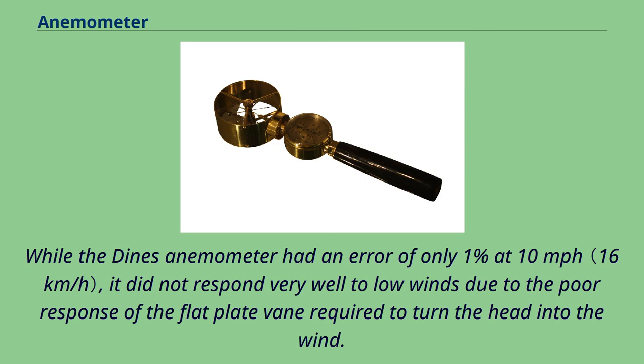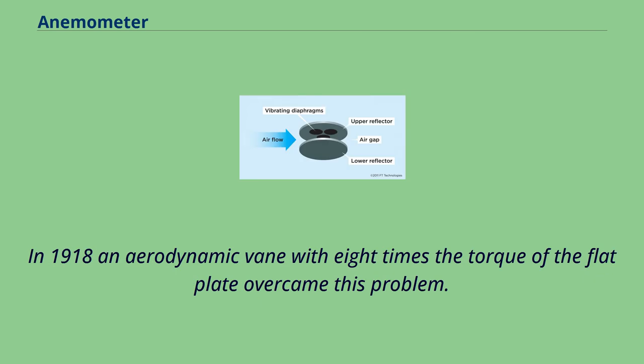While the Dines anemometer had an error of only 1% at 10 miles per hour, it did not respond very well to low winds due to the poor response of the flat plate vane required to turn the head into the wind. In 1918 an aerodynamic vane with eight times the torque of the flat plate overcame this problem.